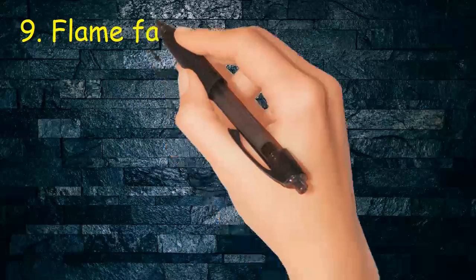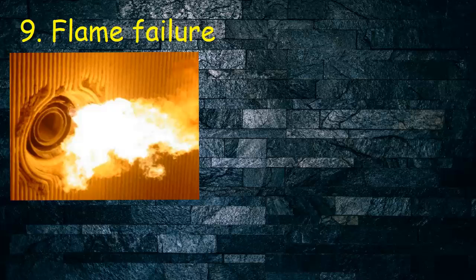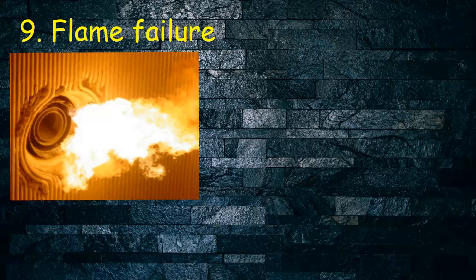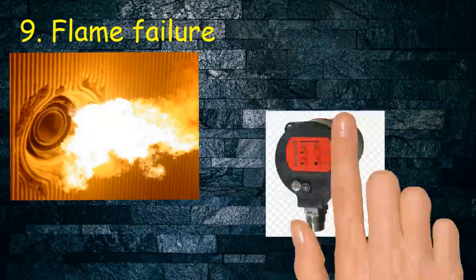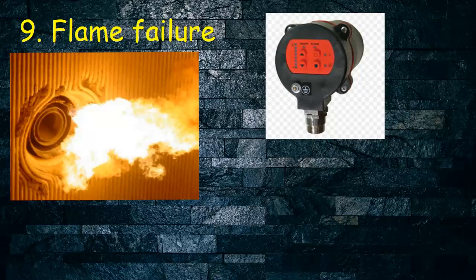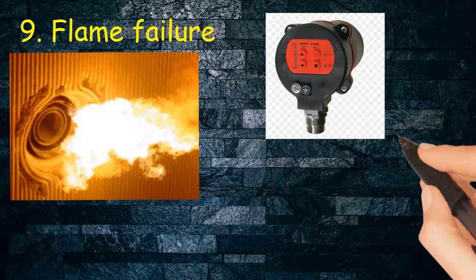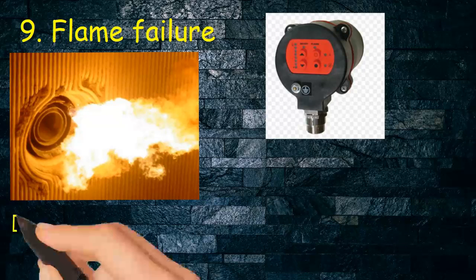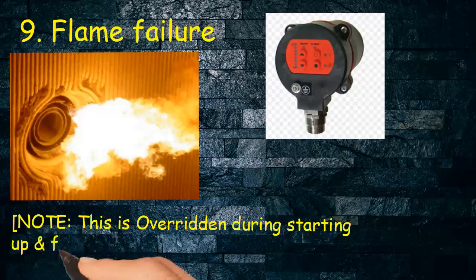Flame failure. The photocell flame eye is used to detect the flame inside boiler. If the burner is abruptly stopped or during starting the main burner is not producing flame, the photocell will detect the absence of the flame and sound an audio visual alarm. Note, this is overridden during starting up and firing up of the boiler.